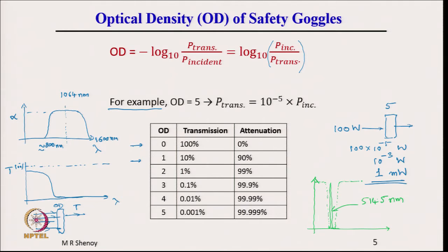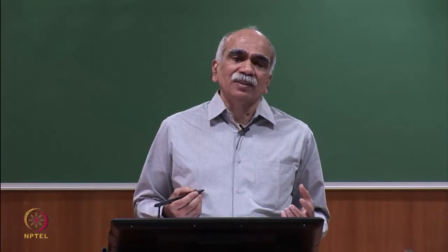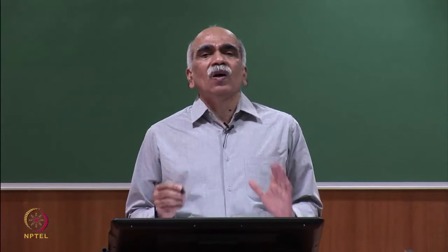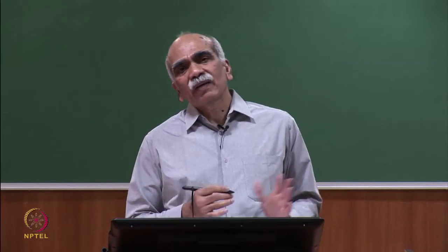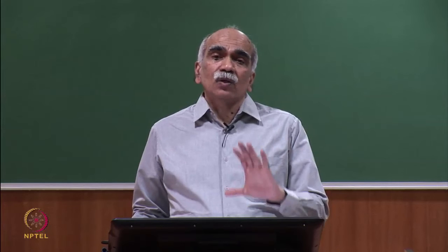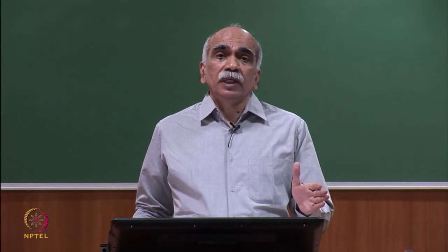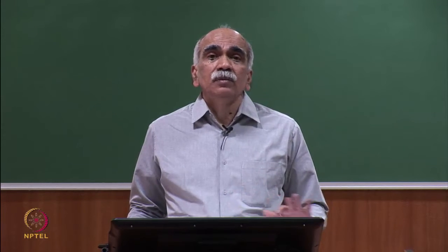If we block the entire region around this line, the goggle will not permit visible light to pass through, and the laboratory would look like a dark room, and you would not be able to see the equipment. So, appropriate goggles have to be chosen. There are several issues involved in choosing the goggle, but the most important is optical density, which has to cut down the laser beam so that it does not harm the eyes.